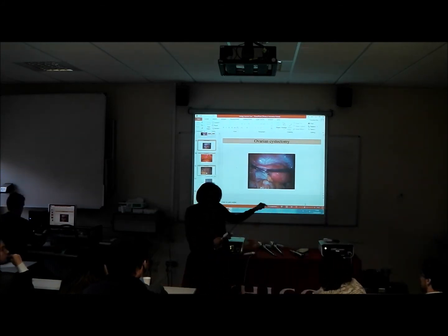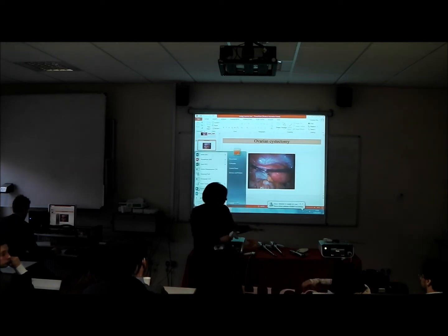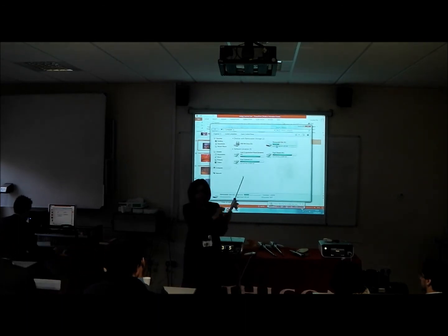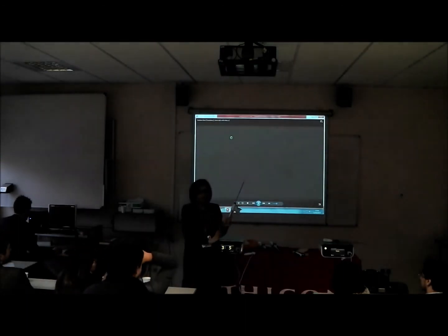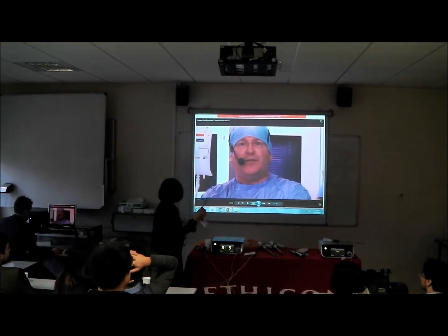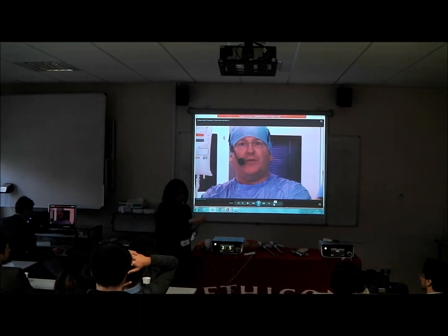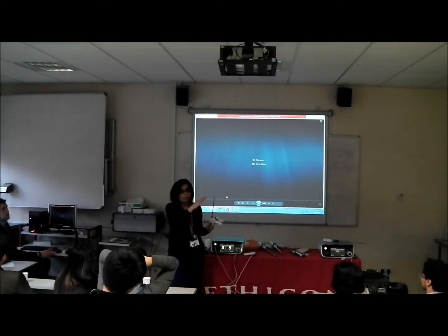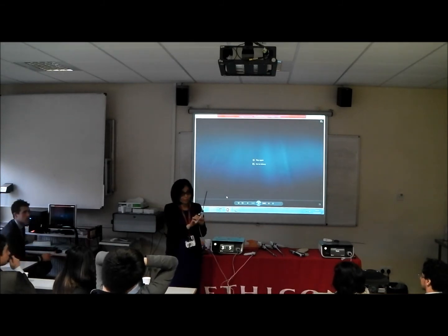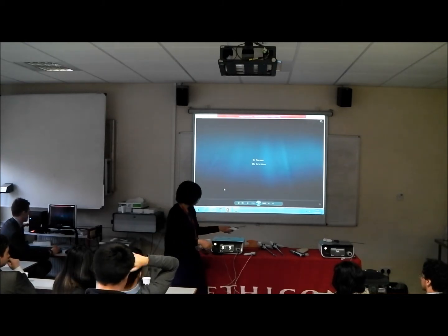So basically, sound energy. This is the generator. It's plugged into the mains. Electricity is coming in. There's a piezoelectric crystal inside the handpiece. This electricity makes the crystal vibrate, and this vibration then travels through the shaft to the two ends of the harmonic scalpel, and they vibrate. They are vibrating at 55,000 times per second, and that's why they are producing heat, because of the mechanical vibration. So Chris is going to show you a little procedure.